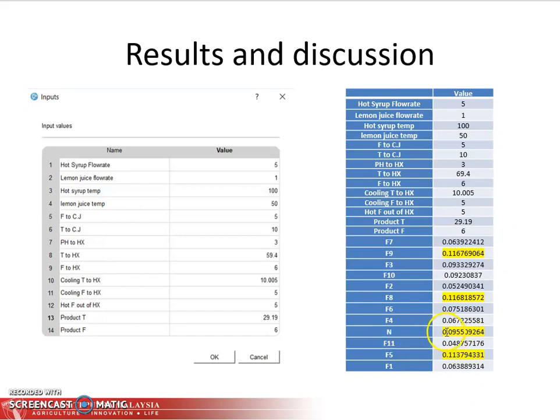So the system diagnosed it as not operating normally, but at the same time no value was dominating, which suggests that it's a new fault. At the same time, it was showing faults for a failure in the heater and a failure in the heat exchanger, which is impacting the temperature because it was sensing a different temperature.